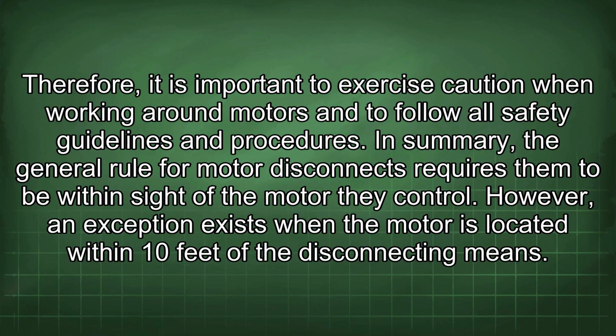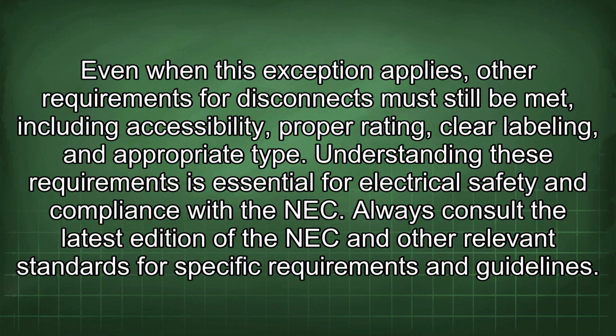In summary, the general rule for motor disconnects requires them to be within sight of the motor they control. However, an exception exists when the motor is located within 10 feet of the disconnecting means. Even when this exception applies, other requirements for disconnects must still be met, including accessibility, proper rating, clear labeling, and appropriate type. Understanding these requirements is essential for electrical safety and compliance with the NEC.